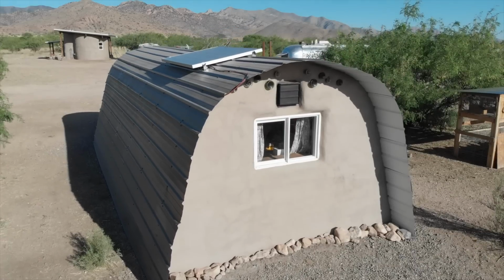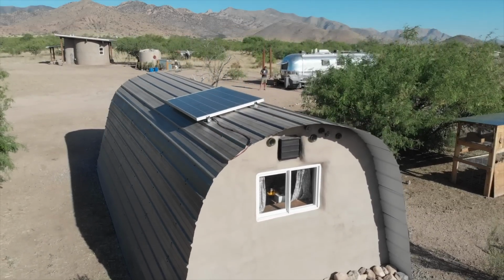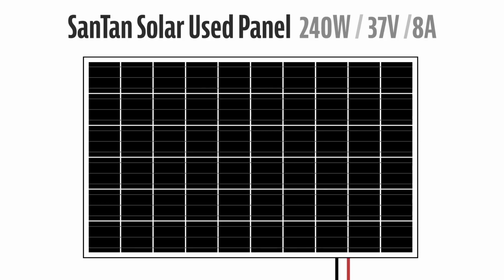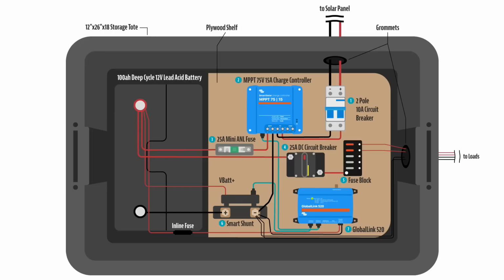We mentioned earlier that we were using a 240 watt used solar panel from Santan Solar. It runs at 37 volts or 8 amps, and generally PV wire is 10 gauge. So you want to start by running the PV positive and negative wire to a 2-pole 10 amp circuit breaker.